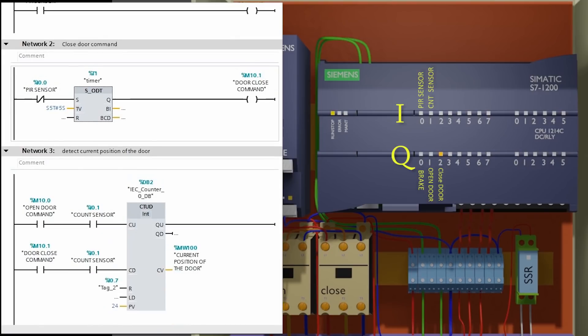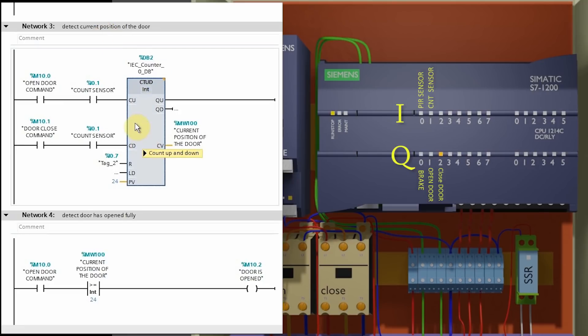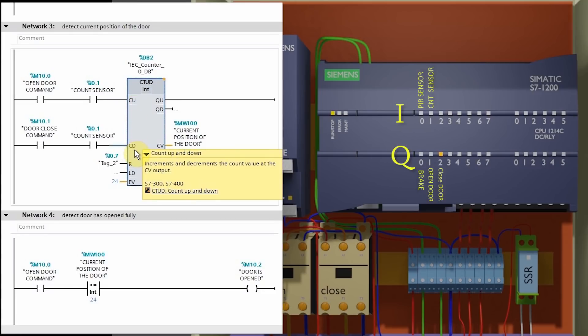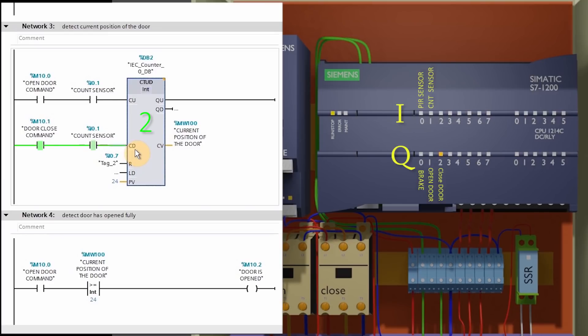Network 3 is to detect the current position of the door so that we have an updated status of the door position at all times. To detect the current position, I have used an up/down counter. It has two inputs — one for up counting and another for down counting. If the open door command bit is on and the count sensor is giving output pulses, the counter will be incremented by one on each pulse at the CU (count up) input. Similarly, if the close door command bit is on and the count sensor is giving pulses, the counter will be decremented by one on each pulse at the CD (count down) input. The current value of the counter is stored in memory word 100.